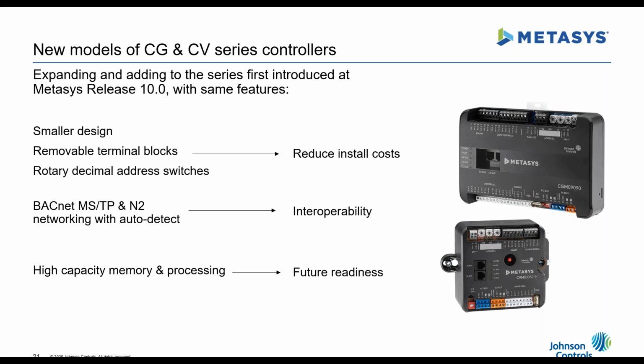This family includes models that support BACnet MSTP and are software switchable for N2 networking, enabling these controllers to be interoperable with N2 networks without needing to purchase a special model and without any extra setup, since these controllers will auto-detect the communication protocol they're connected to. The new family of equipment controllers also have faster microprocessors with significantly more memory, which enables support for our new software features and leaves ample room for future software upgrades.